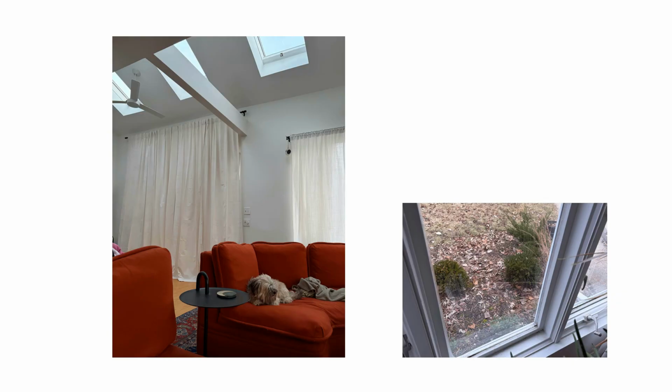And on the right, you can kind of see, hopefully you can see, there's condensation on the inside of those windows. Sometimes we get it on the inside of the walls too. But we're lowering the surface temperature of the inside of those walls in order to save the rest of the house. But in this case, that's bringing it below the dew point of the rest of the indoor air. And so when the indoor air makes its way through and around those curtains, we get condensation on those windows.